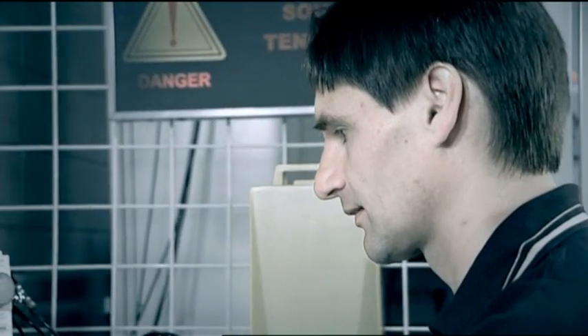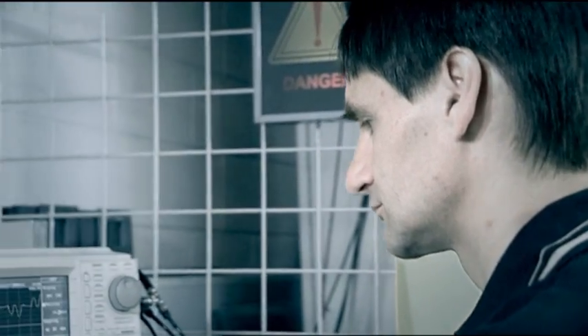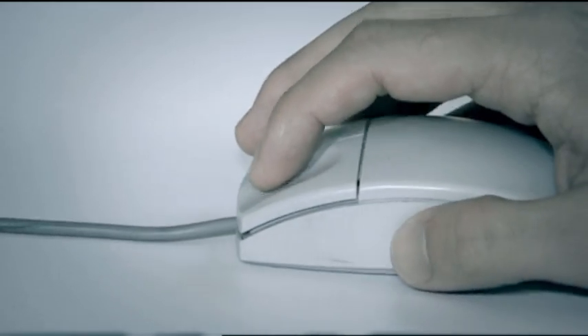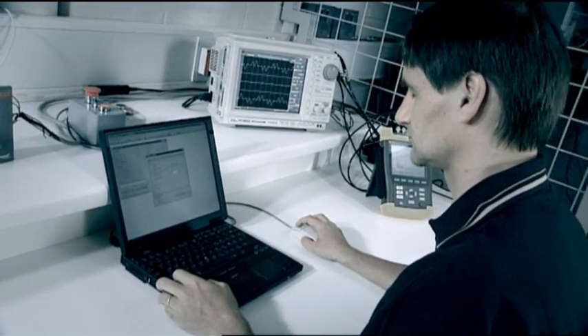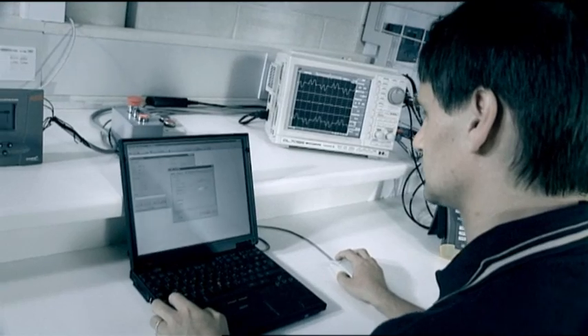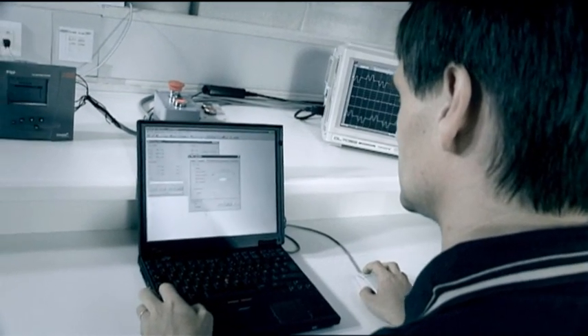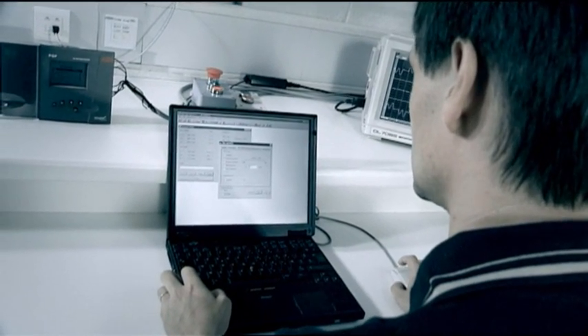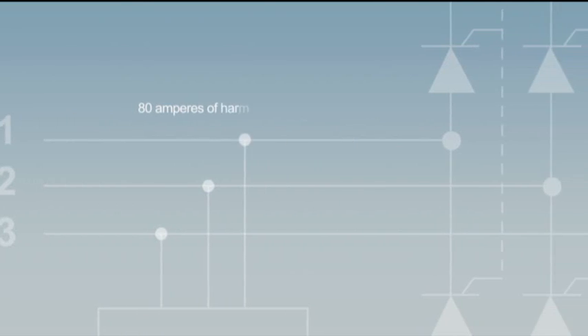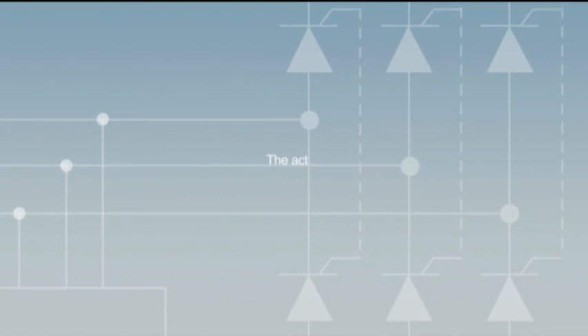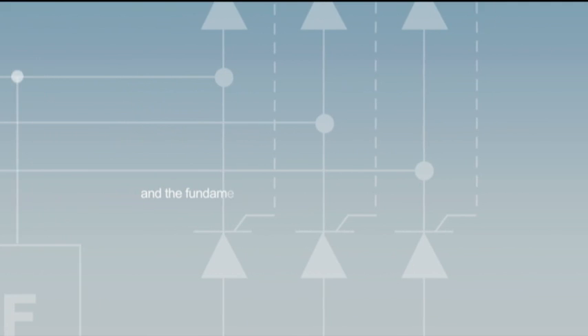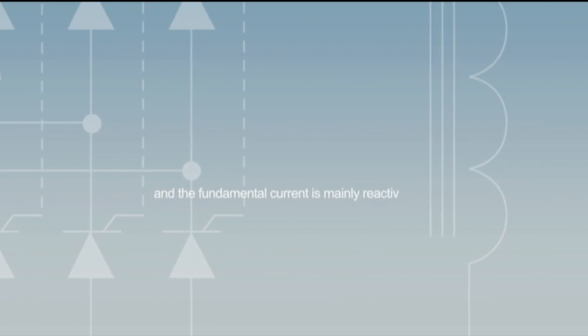You'll now see a real demonstration of the ABB active filters performing harmonic filtering, power factor improvement and load balancing. For the first demonstration, the load used is a 6-pulse Thyristor rectifier connected to a DC reactor. This load generates about 80 amperes of harmonic current. The active power consumption is low and the fundamental current is mainly reactive.